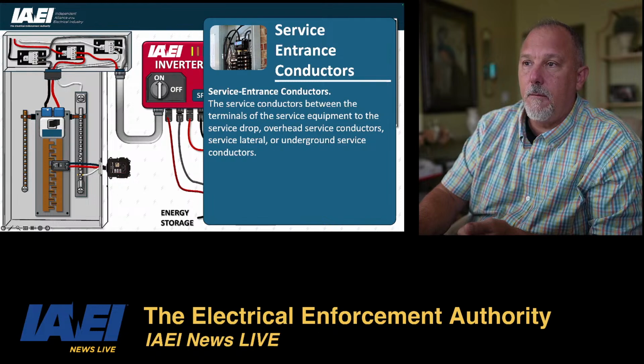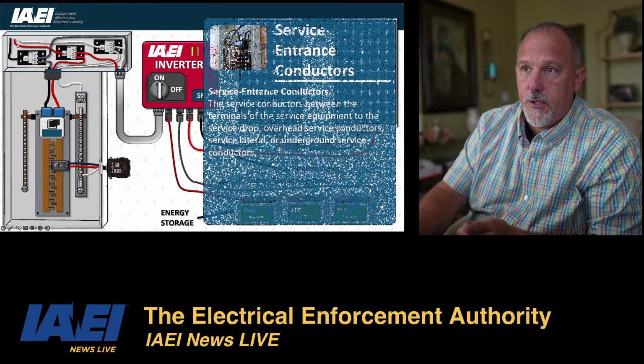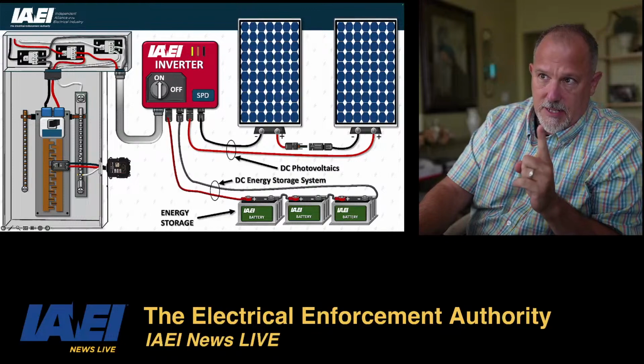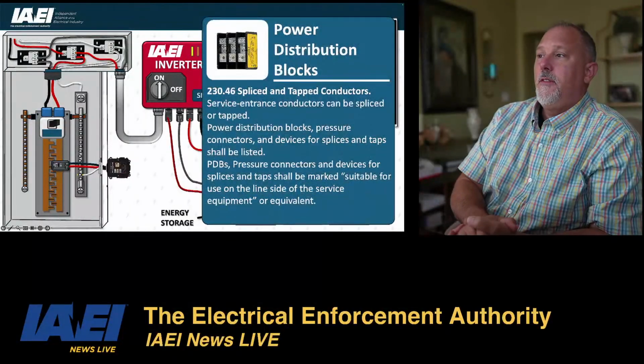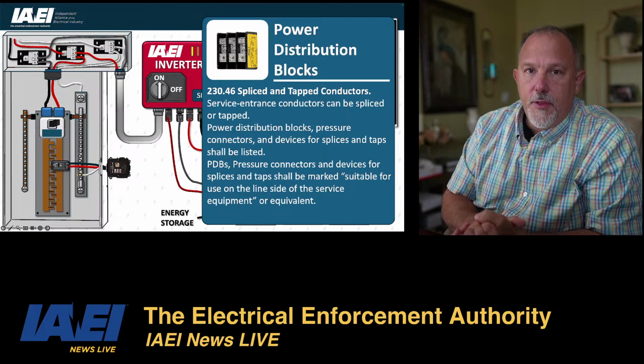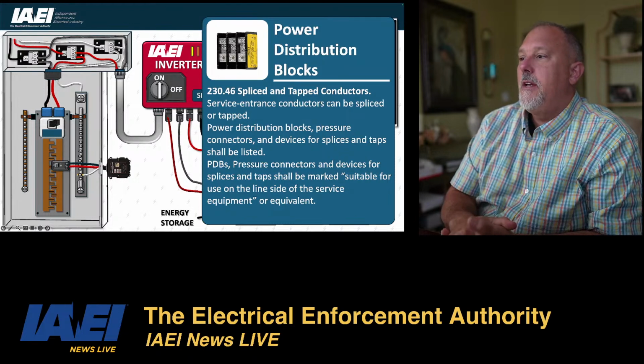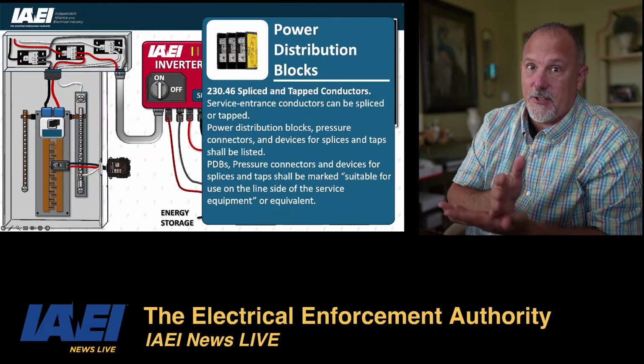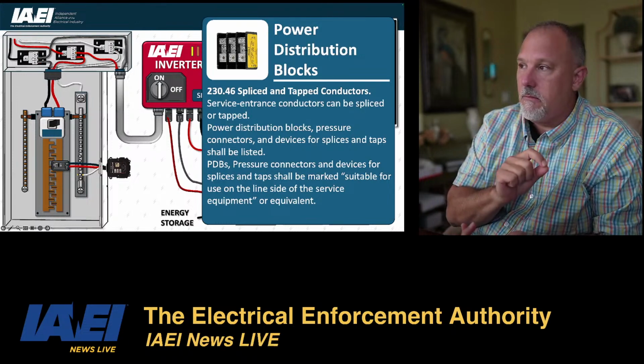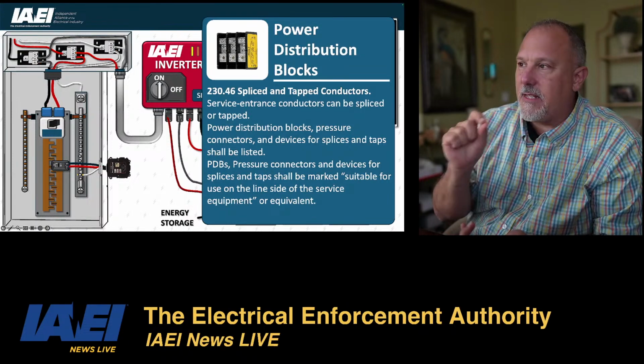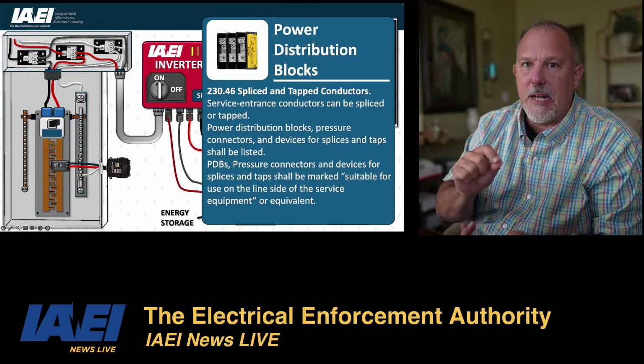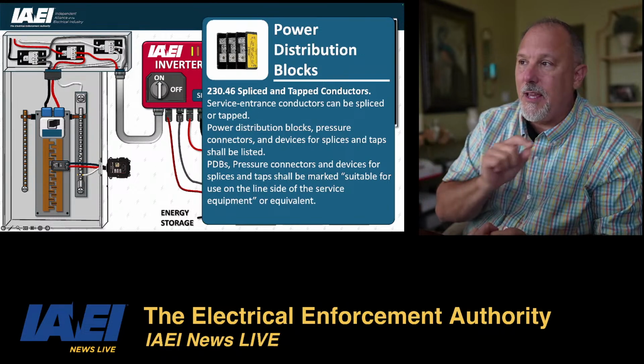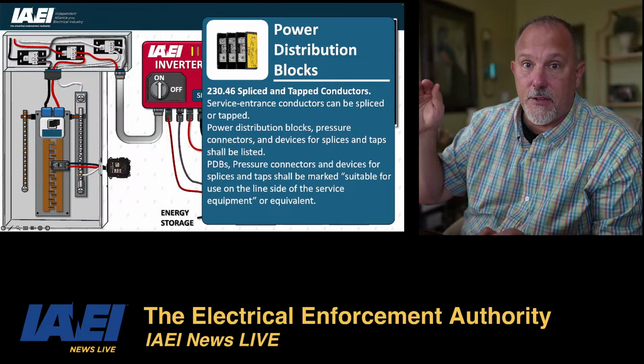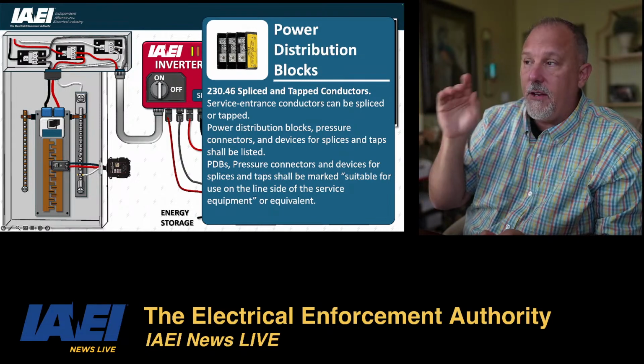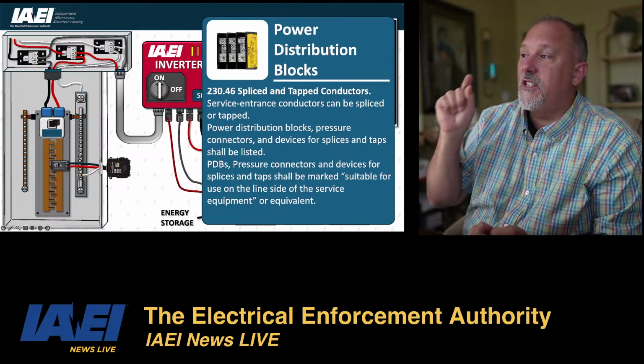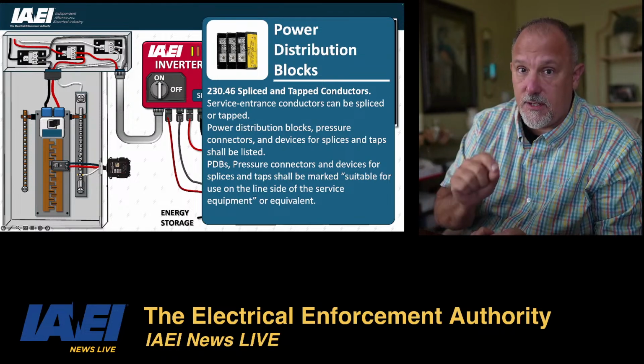All right, so those service conductors. Now let's talk about these power distribution blocks. These are in 230.46. These are service entrance conductors. So that means you can't splice and tap a service drop. You can't splice and tap a service lateral. You can't splice and tap overhead service conductors. But you are permitted in 230.46 to splice and tap service entrance conductors.